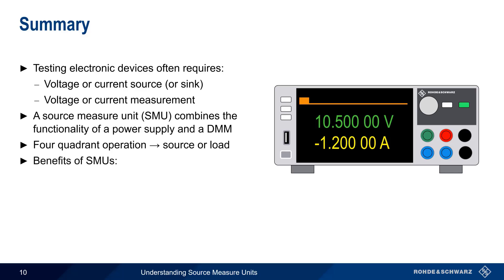Source measure units provide numerous benefits. Since they can replace multiple instruments, they take up less bench space and reduce overall equipment cost. Easier synchronization enhances both manual and automated operation, and the shorter settling time provided by most SMUs means faster measurements. And finally, source measure units provide higher precision than stand-alone power supplies or multimeters.